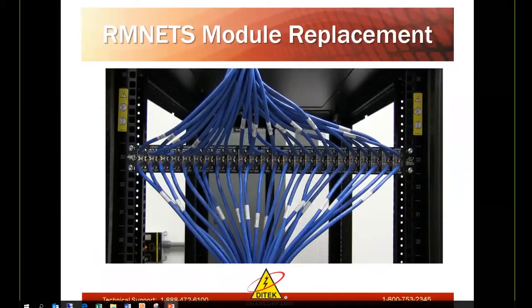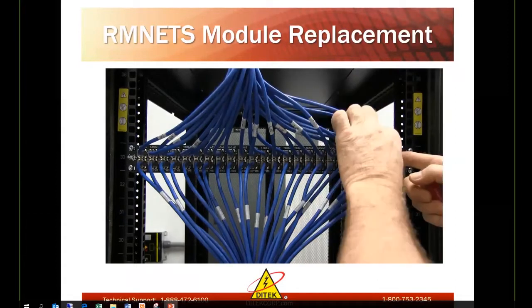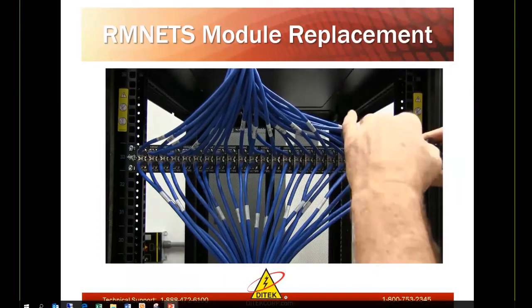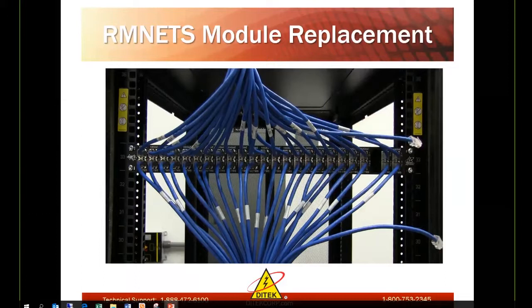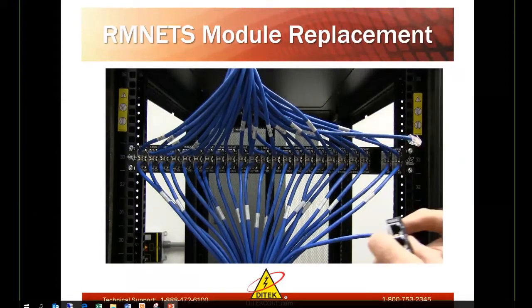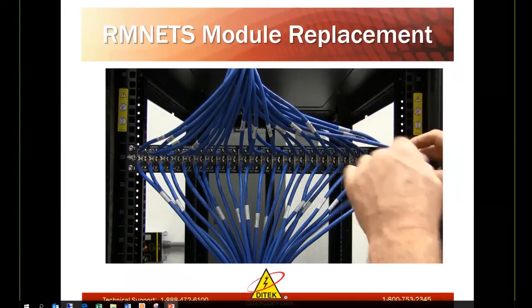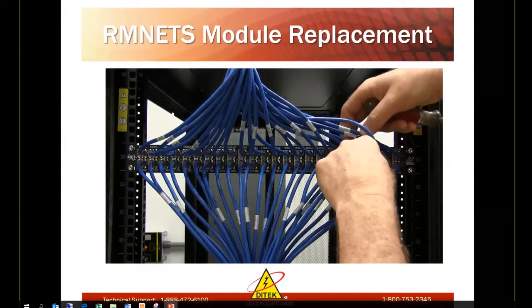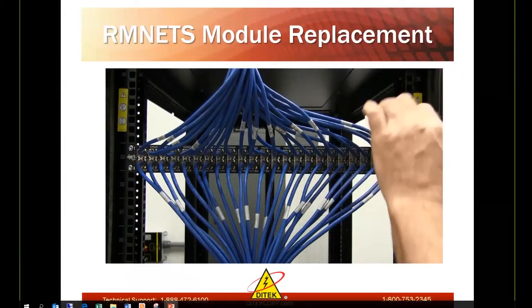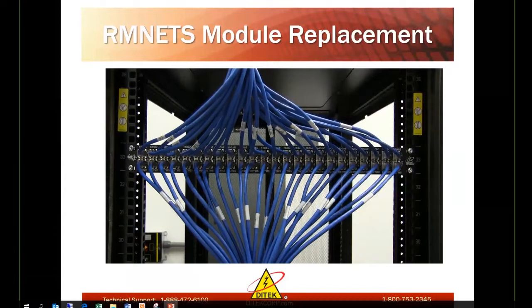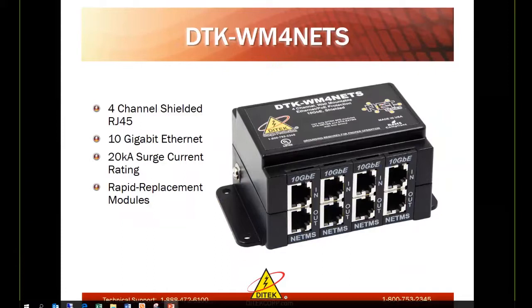If a surge module ever needs to be replaced, it is just as simple as opening up the bezel from underneath and from the top, and then you just simply slide the unit out, disconnect your circuit, and then replace it with a new one. So you can see how easy it is to replace those modules. You actually don't even need a screwdriver. We've actually done it with coins, such as nickels or dimes, to pop those out.